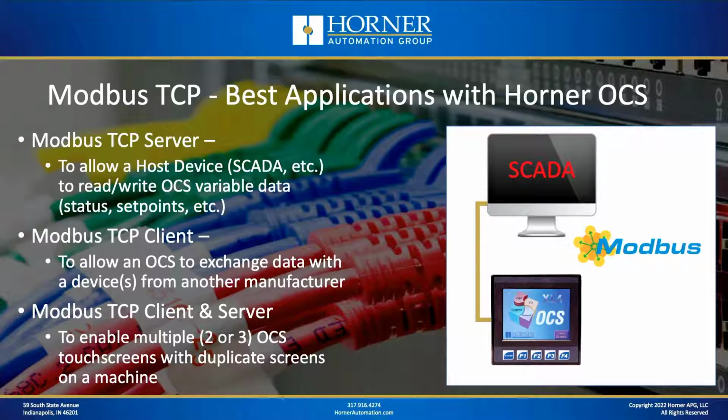If you have more than 2 or 3 different OCSs involved with this specific application, you're probably going to be better off with Ethernet Global Data. But if you're just talking 2 or 3, you can get some excellent response times with Modbus TCP.